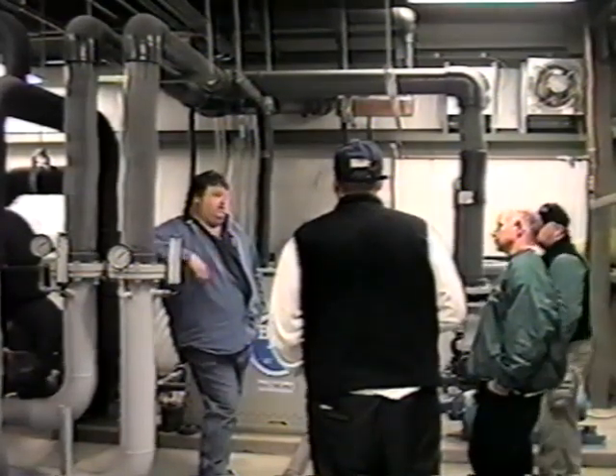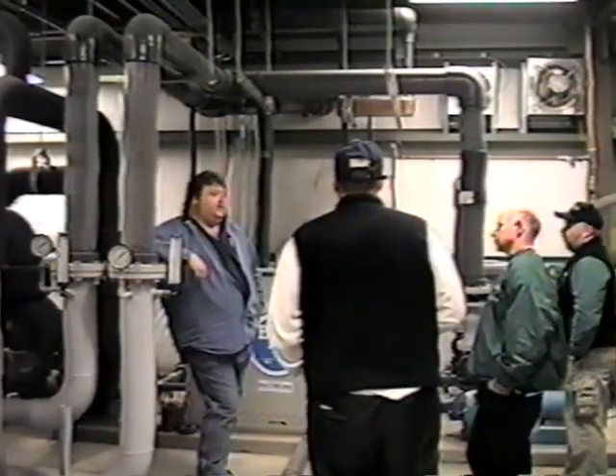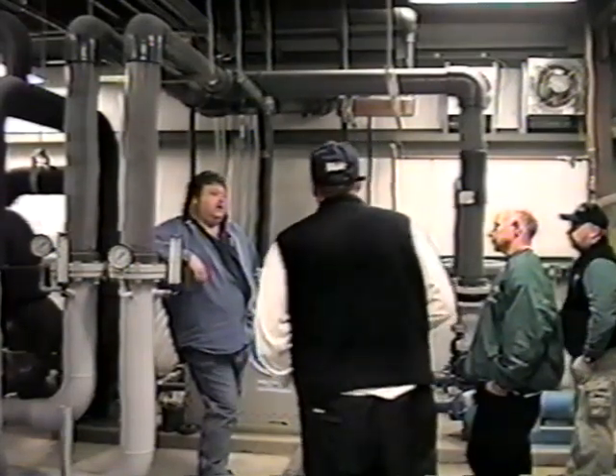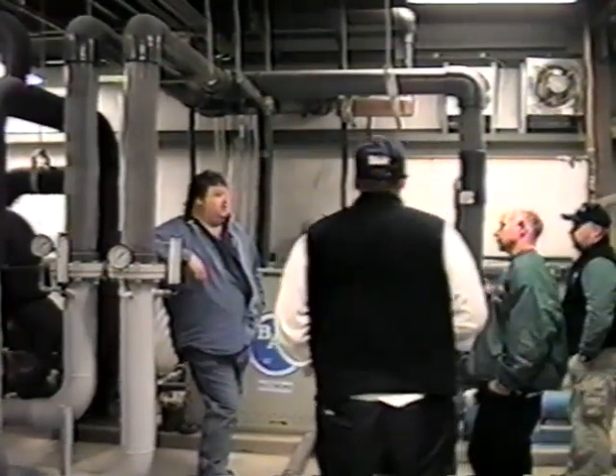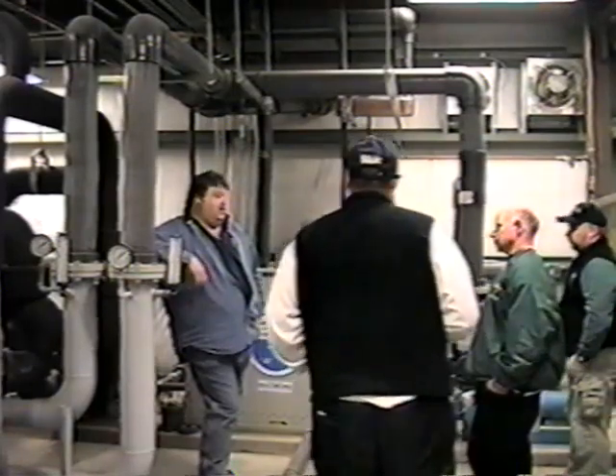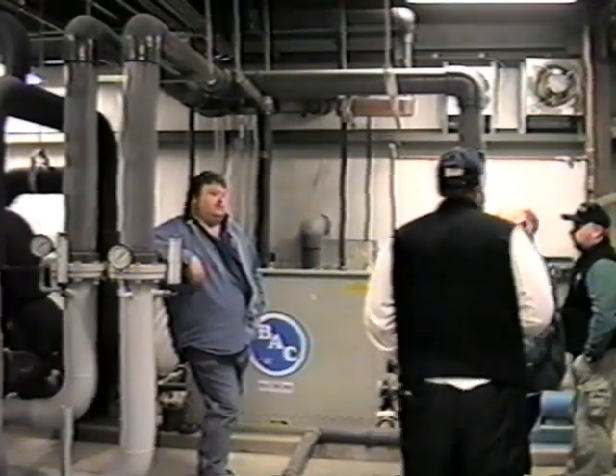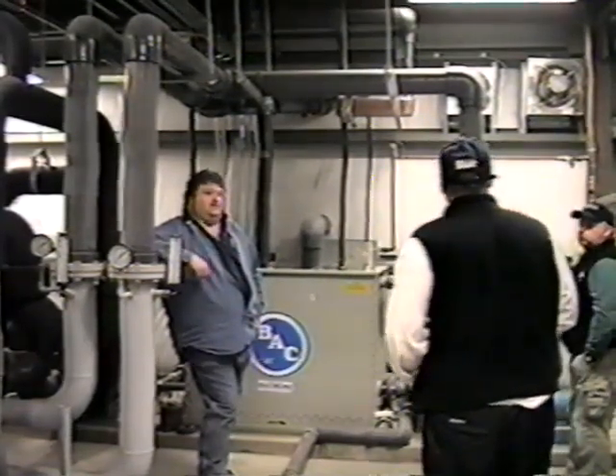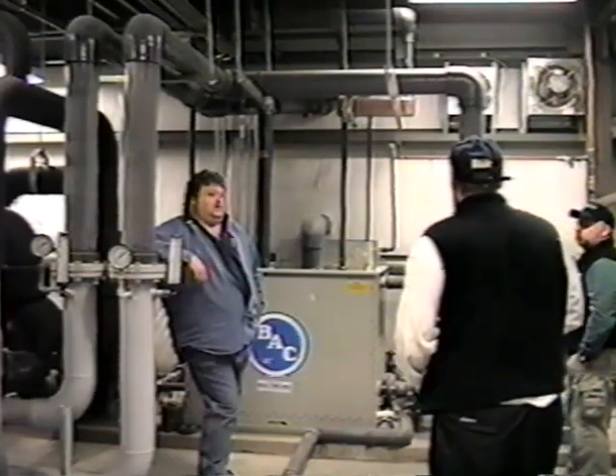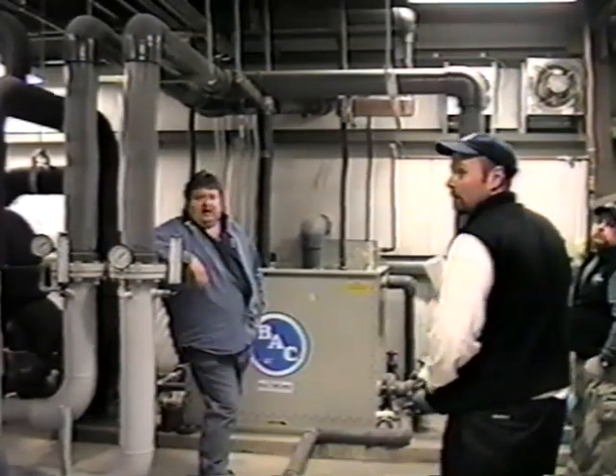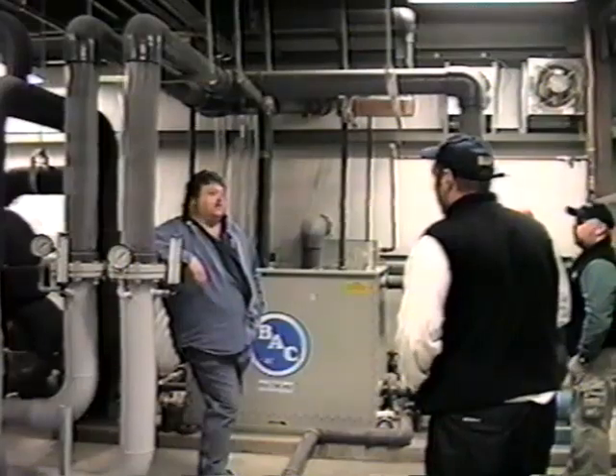If you open the door and you had a small ammonia leak in here, you know it, and you know how severe it is too. Because if you open the door, your eyes water, it's bad. We had a couple bad ones. You'd smell it right out on the ice, the back end of the ice or something. It's that bad. Like I say, I kind of prefer it because you can narrow it down a lot quicker as to where it's coming from.